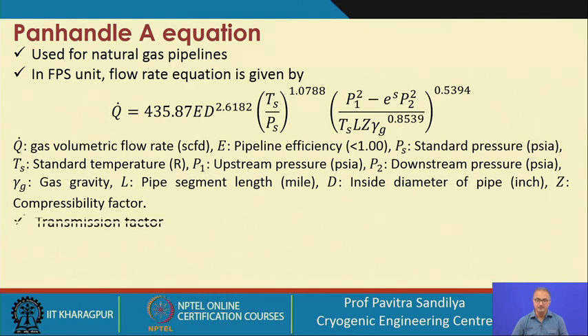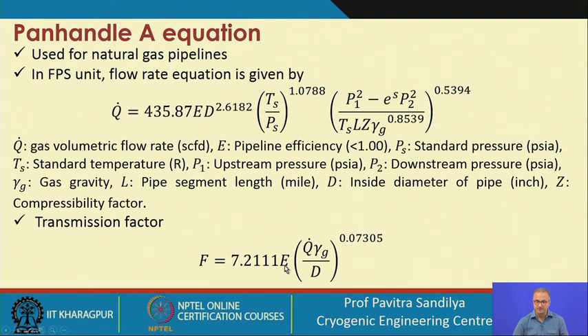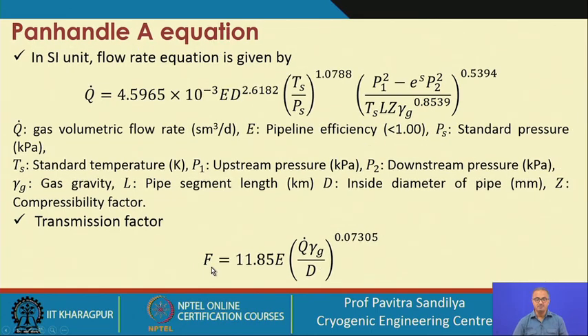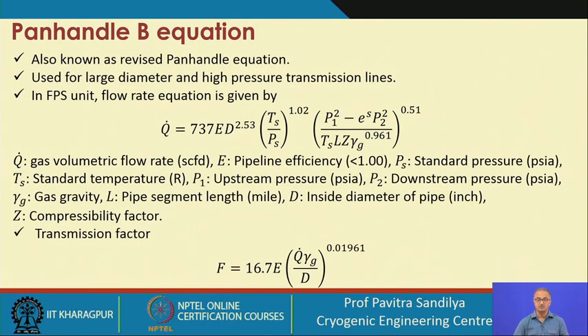The transmission factor can be given in terms of the pipeline efficiency, the volumetric flow rate, inside diameter, and gas gravity. The same Panhandle A equation is given in terms of SI units — the particular constant value has changed while the rest of the terms remain the same. The transmission factor expression has also changed slightly due to the change in the particular constant.